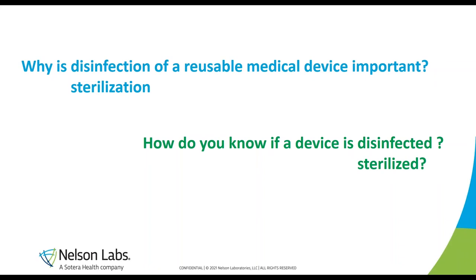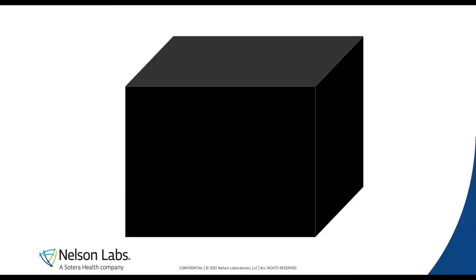How do you know if a device that has been reprocessed is disinfected or sterilized? Can you look at the device and see whether the procedure was performed correctly? When you clean a device you can see whether it is clean, but if a device has been sterilized you actually do not know whether the process was performed correctly. I call this a black box — you just have to rely on the process.